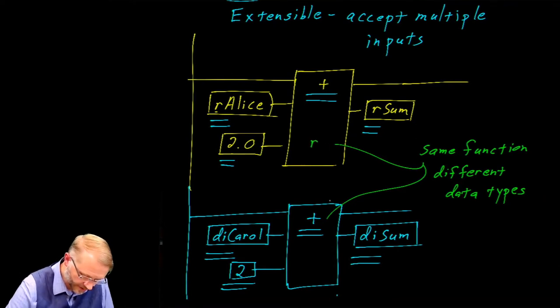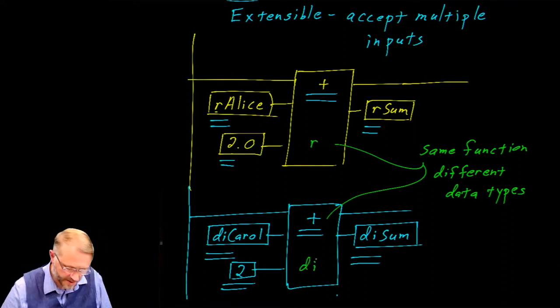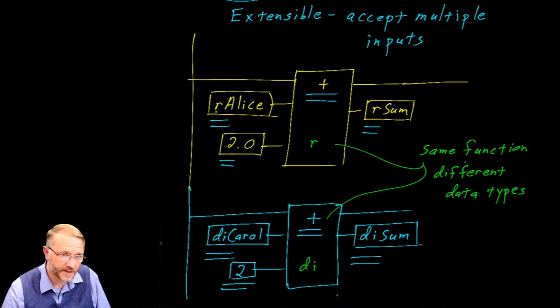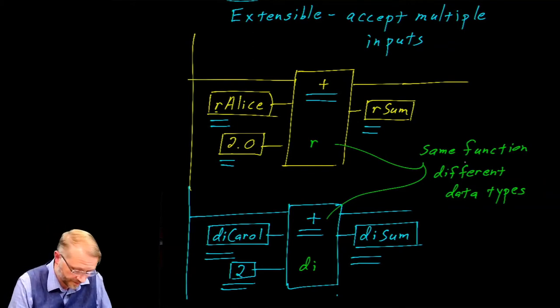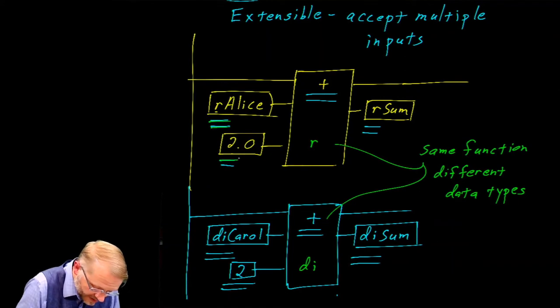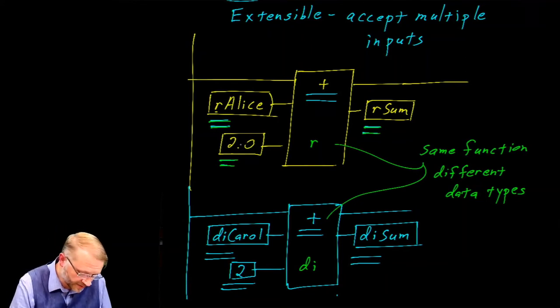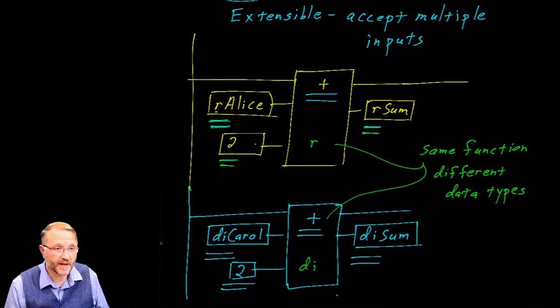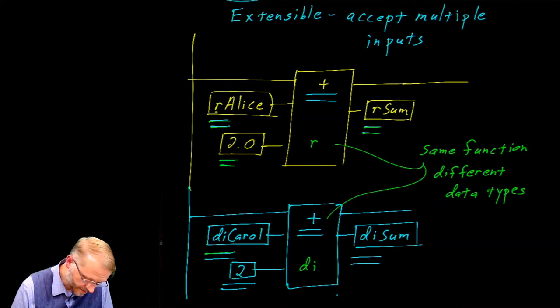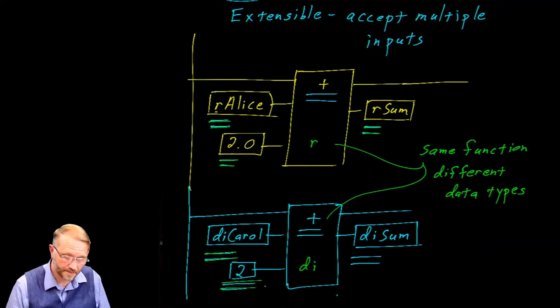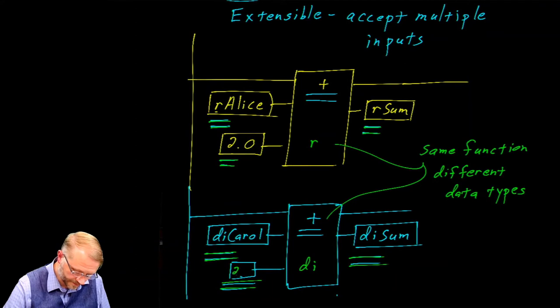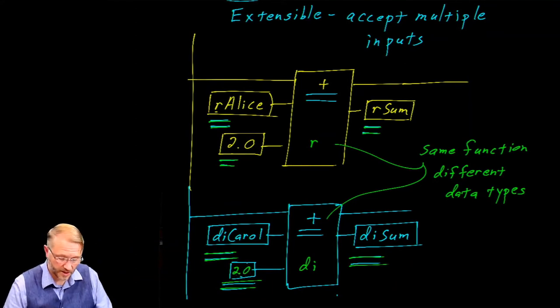While the function will operate on different data types, that does not mean you can mix and match data types on an individual function. Both inputs are type real and the output is type real — you cannot change that. For example, if you set one input to 2 (an integer), you would have an error because 2 is not a type real. We see the same thing with double integers: all inputs and the output must be the same type. If you were to set an input to 2.0 (type real) in a double integer function, you would have an error.